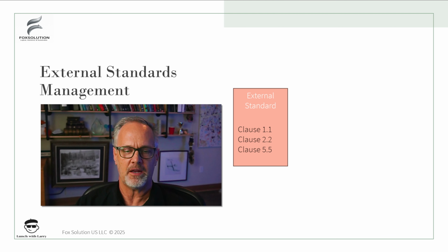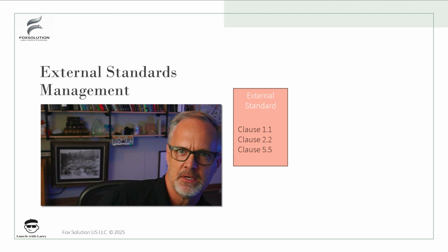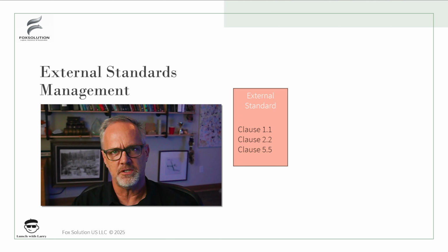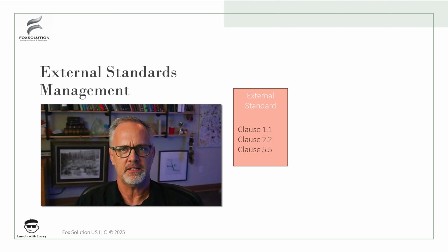And when we talk about external standards, I'll give you some examples. Maybe 11135, which is ethylene oxide sterilization of medical devices. Maybe 60601, electrical medical device requirements, ISO document. There's also ASTM standards for testing. There's IEC, IEEE, right? All these different agencies that have committees that sit around and decide for a particular scope of work what requirements are necessary to assure that a device gives you the performance that it needs.